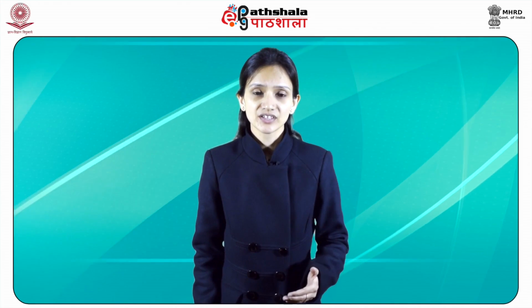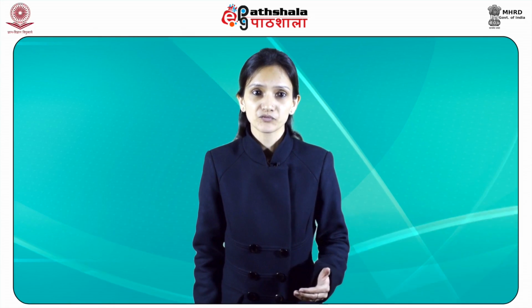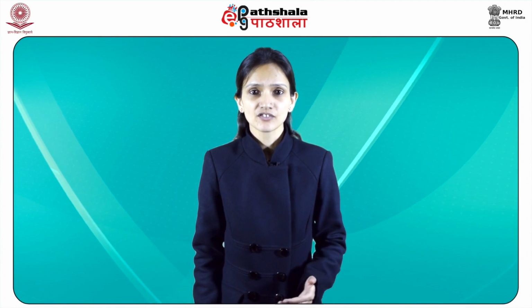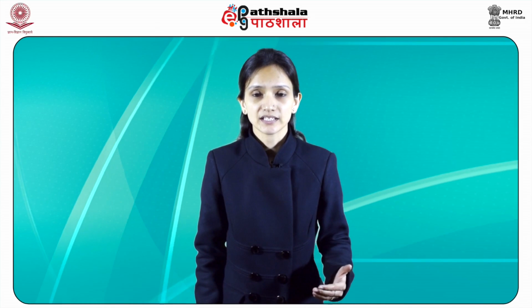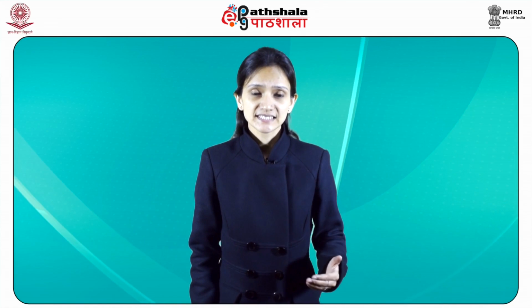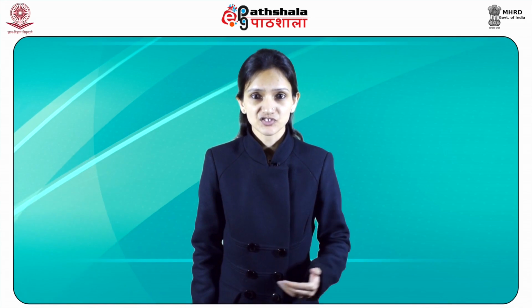As concentrations decrease to trace levels or as signal sources become weak, the problem of distinguishing signals from noise becomes increasingly difficult, resulting in decreased accuracy and precision in measurements. The ability of an instrument system to discriminate between signals and noise is usually expressed as signal to noise ratio, that is S/N, where S/N is equal to average signal amplitude upon average noise amplitude. In the case of DC signals, an increase in the S/N ratio usually indicates a reduction in noise and thus a more desirable measurement.